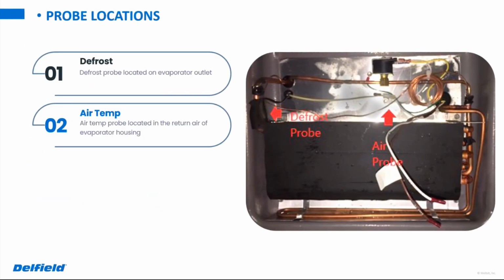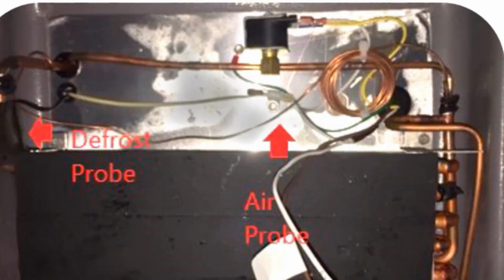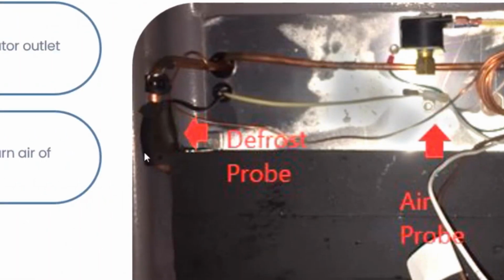As far as probe locations go, we have the 2 probes on these. Again, they'll be on that harness. You have the air sensor. It's going to be located behind the evaporator cover. It's typically a small little plastic clip that it goes into. The defrost probe on this isn't actually a true coil probe. It actually mounts to the suction line. So you won't find it in the evaporator coil.